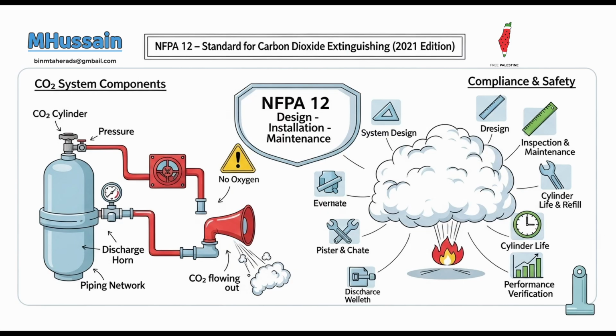And deeper maintenance. Maintenance is required at least annually, going far beyond the monthly inspection. Yearly maintenance. This involves a more thorough verification of the system's operation, reviewing the hazard configuration, ensuring the size, type, openings, and fuels haven't changed in a way that compromises the design. Check if the room or hazard changed. And testing all time delays, alarms, both audible and visible, warning signs, and detectors. Discharge tests are performed, if advisable. Test everything annually. How about the CO2 levels?